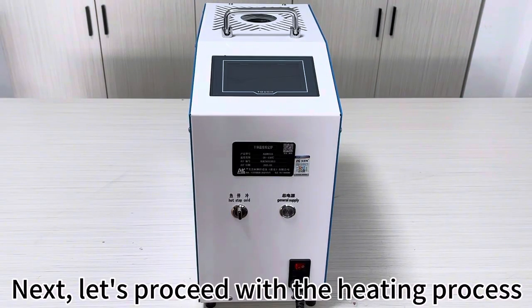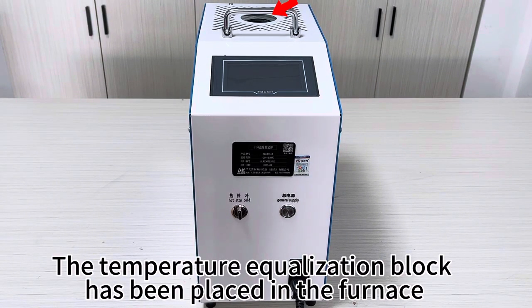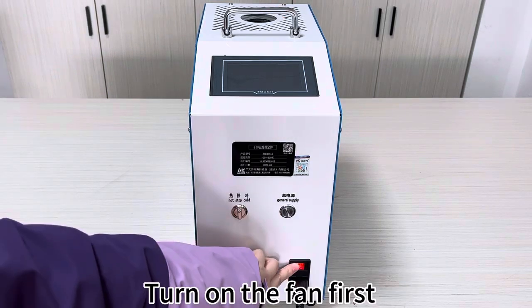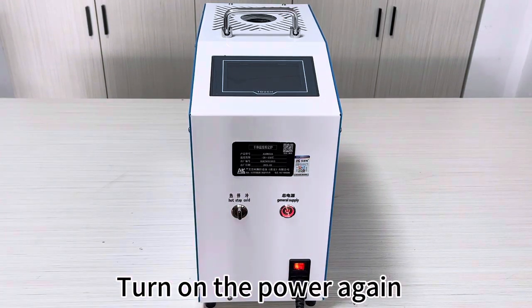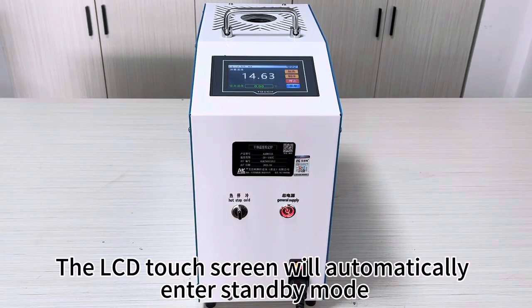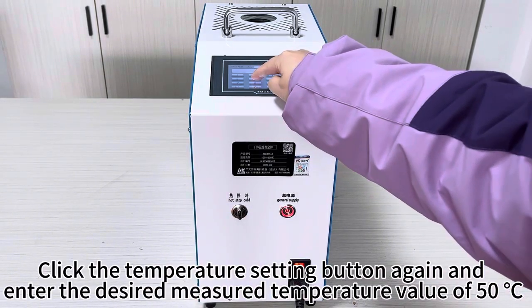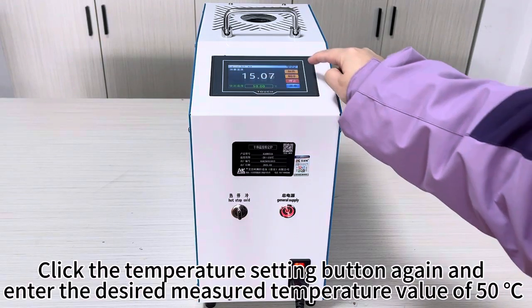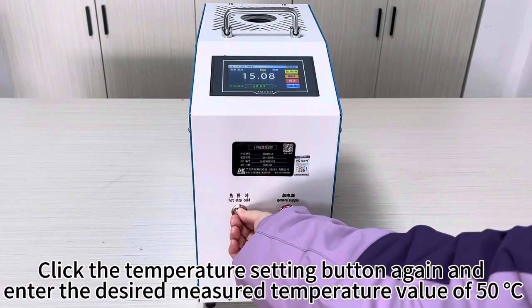Next, let's proceed with the heating process. The temperature equalization block has been placed in the furnace. Turn on the fan first, turn on the power again. The LCD touch screen will automatically enter standby mode. Click the temperature setting button again and enter the desired measured temperature value of 50 degrees Celsius.